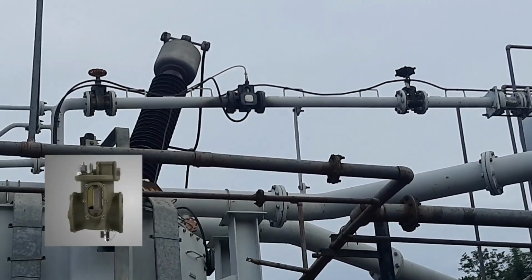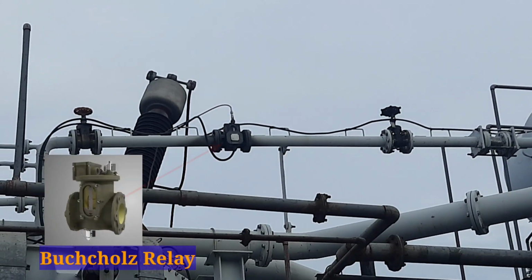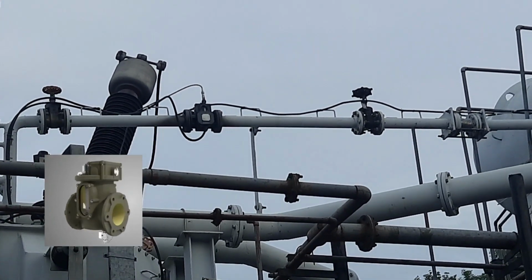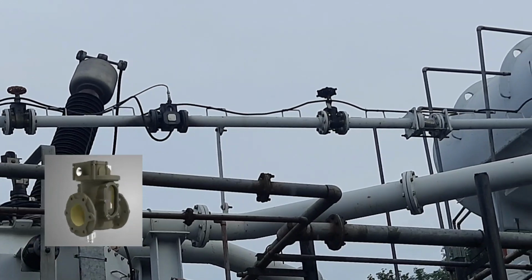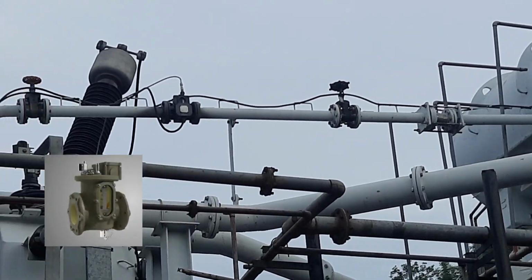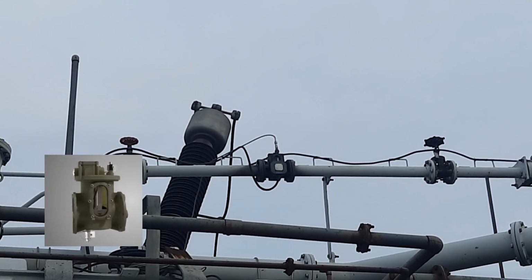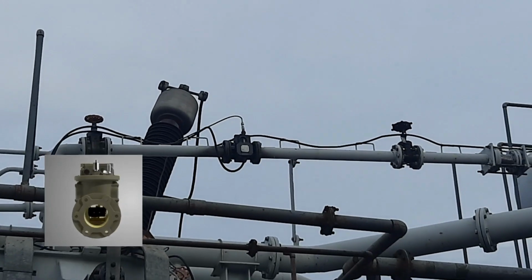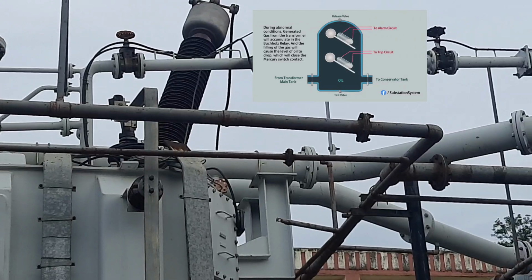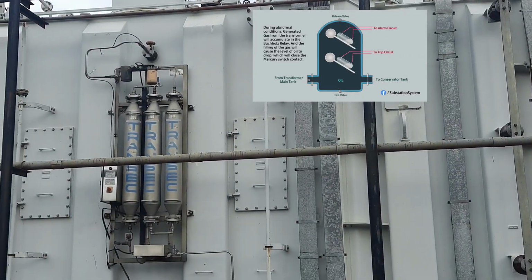This is one of the main relays giving protection to the transformer. In addition to the pressure relief device, the oil surge relay and all those things, WTI, OTI, we have this Buchholz relay. It is a gas actuated relay, based on the formation of gas.